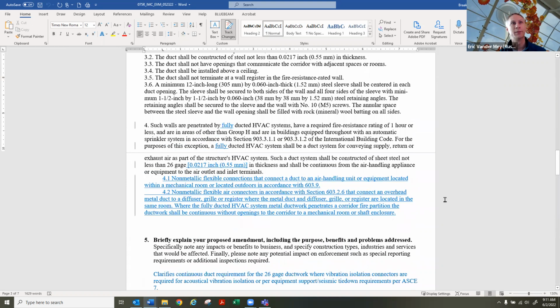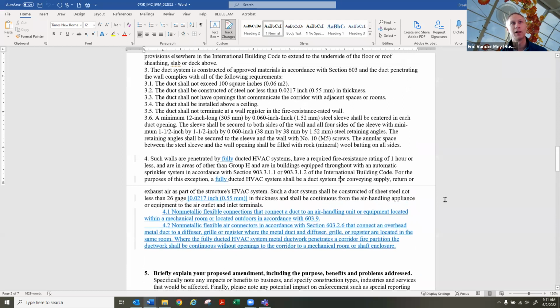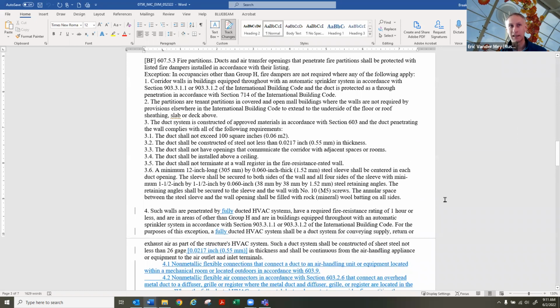And then it does allow for the final connection to the diffuser to have the non-metal flexible air connector. So that really clarifies what I was trying to clarify in my proposal for the fire barriers. So then in fire partitions, I don't know why they chose to only propose this for the fire barrier section, but I'm proposing making these same clarifications for the fire partition section of the code. So adding the words fully ducted to mimic what they did above, and then to provide the same clarifications for the non-metal connections at the units.